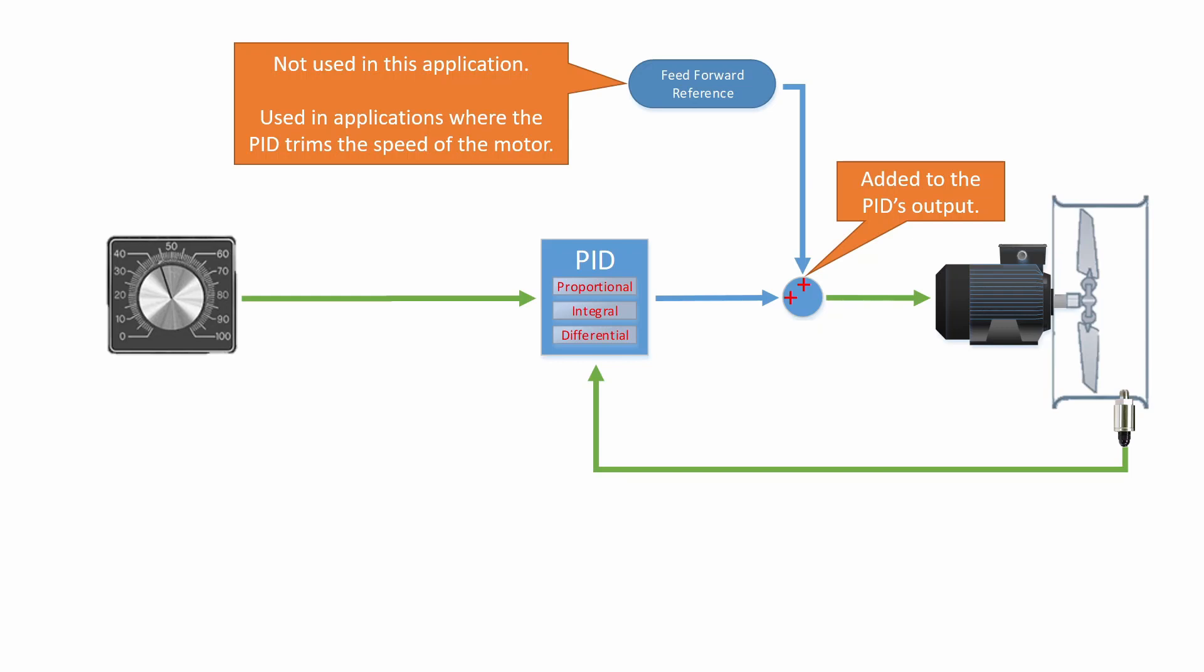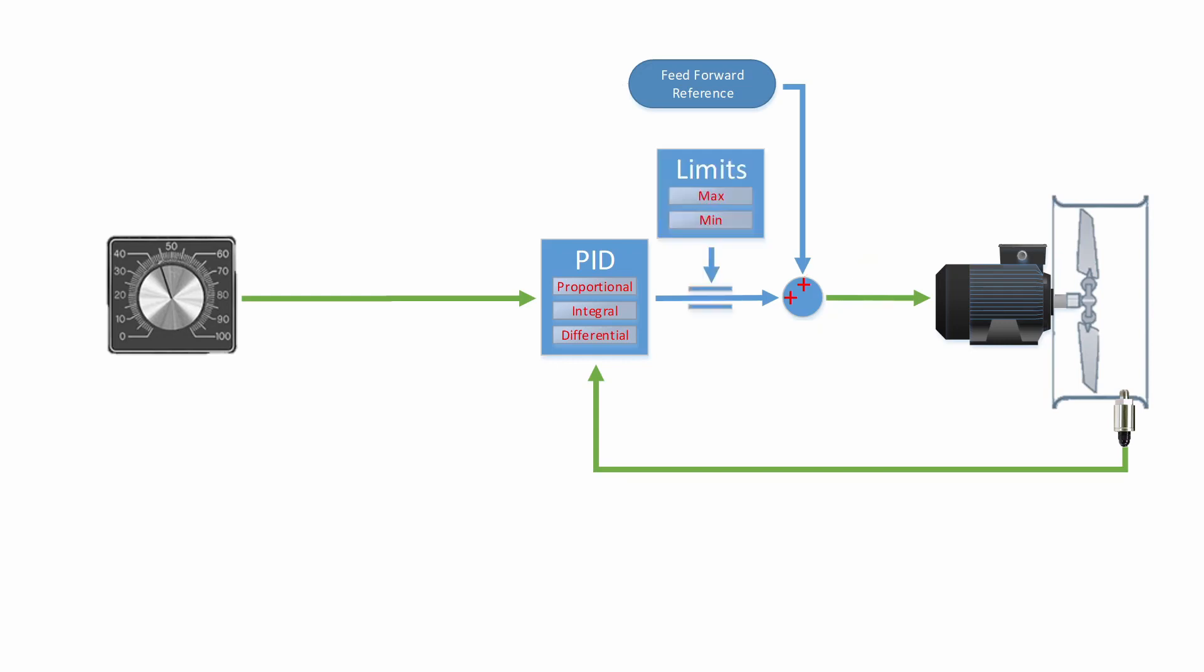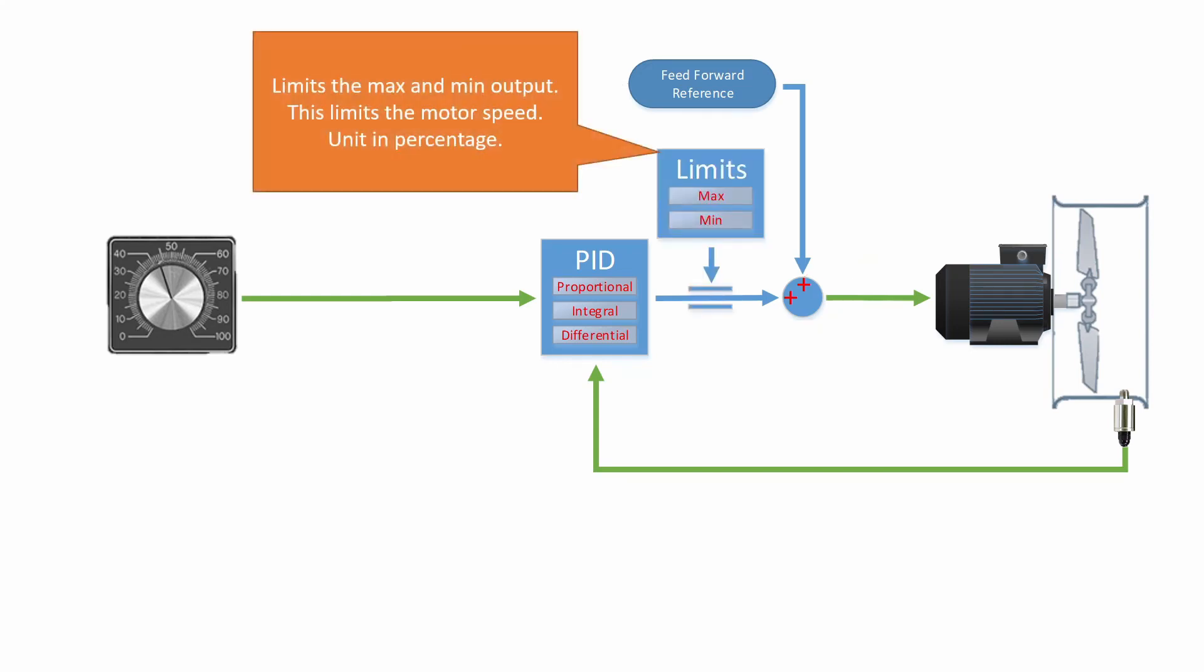An example of this would be a dancer arm. Also on the output side of the drive, there are max and min limits. These are used to limit the output of the PID. This can be used to limit the max speed and the min speed of the motor. For example, you probably don't want your fan running in reverse, so you would set the minimum speed to zero and the max speed to 60 hertz.